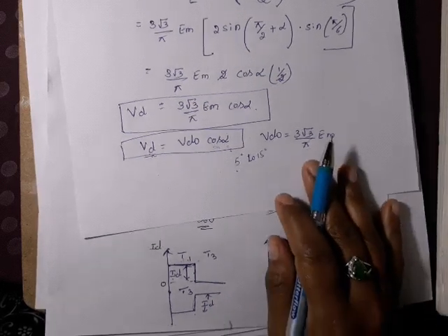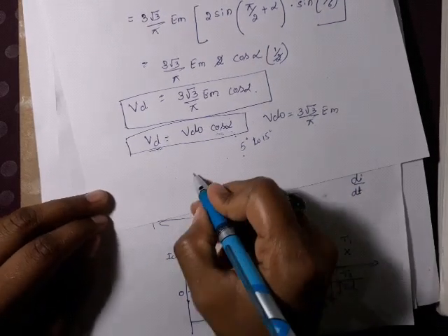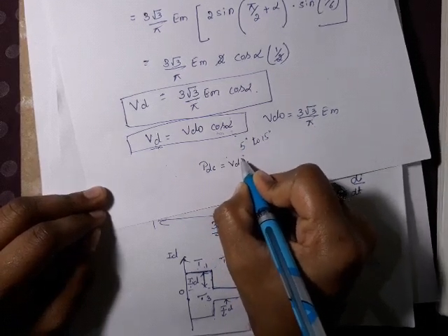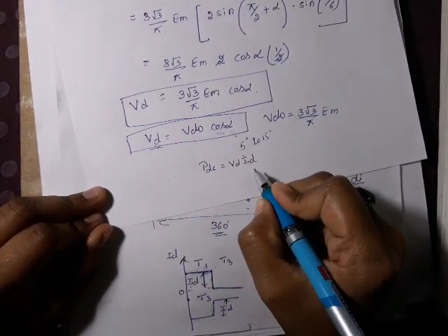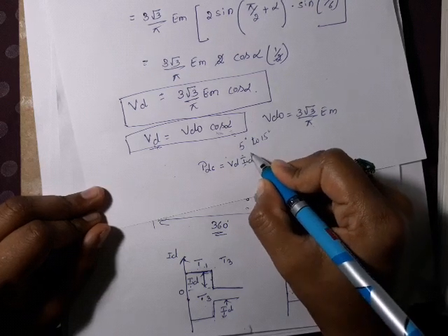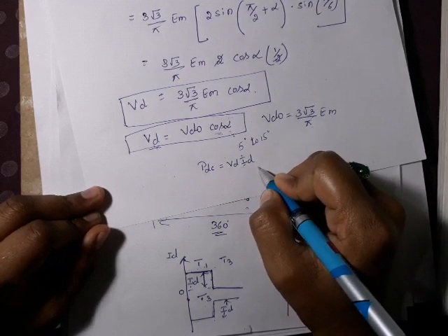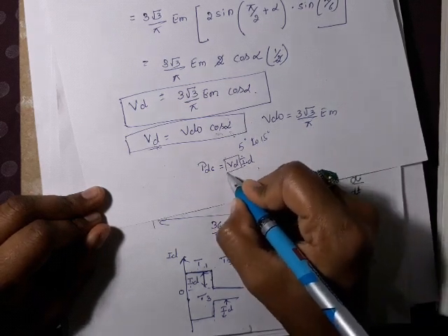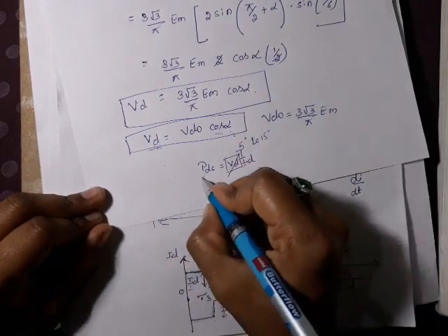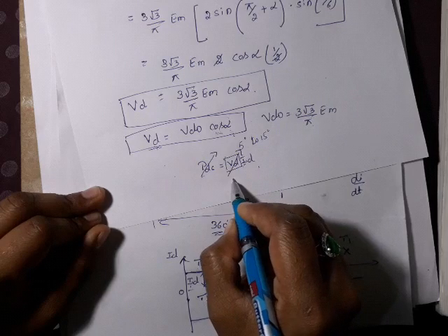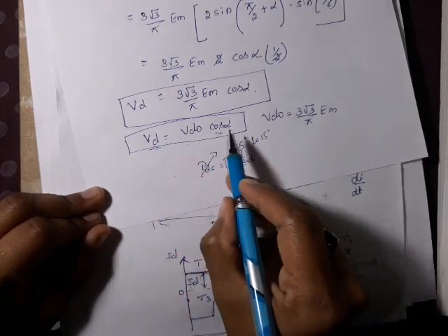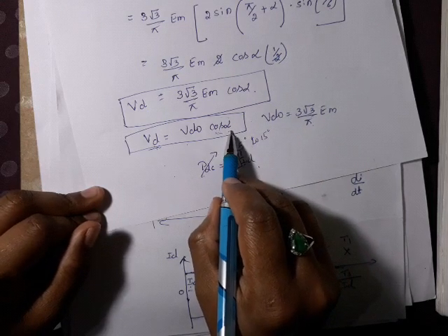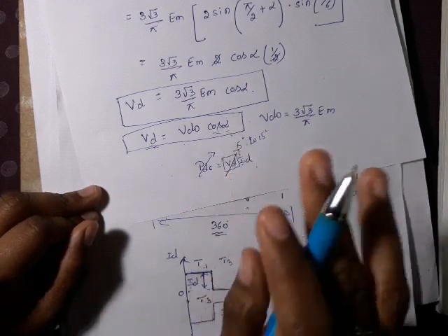No problem. But in case of an HVDC circuit, the power equation is given by VD into ID. In any HVDC line, we are not controlling ID. ID is constant. How can we control the power? The only way is by controlling VD. VD is the variable to vary the power. So how to vary VD? This thing is constant, so we have only one value, alpha. For this reason, we have to vary alpha. We cannot trigger it at exactly 0 degree.